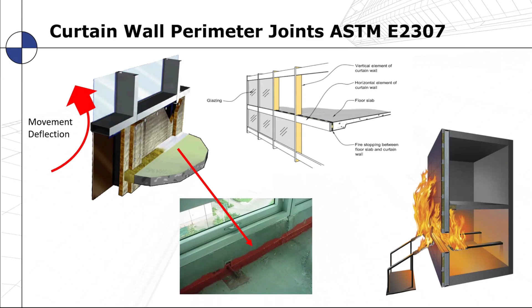But you have to fill that in to keep fire from penetrating and traveling through that opening. And it has to be filled in with a material that is flexible. And generally, a Firestop spray material is used in those kinds of applications. And on the bottom right there, where you see that flame, that is a Firestop test apparatus. It's a 2-story apparatus that's used for testing curtain walls. And so there's a fire set on the inside of the structure that tests the floor portion of the Firestop perimeter joint. And then also a flame is placed on the outside face of the curtain wall to determine how quickly the fire moves up the face of the opening.